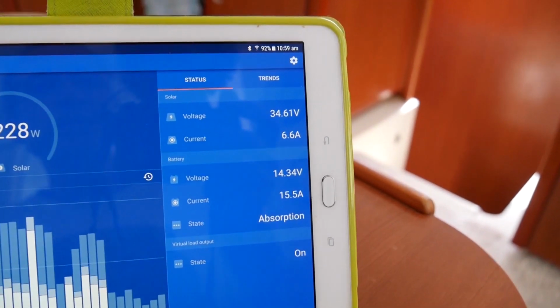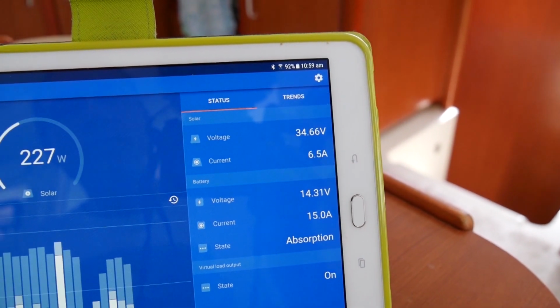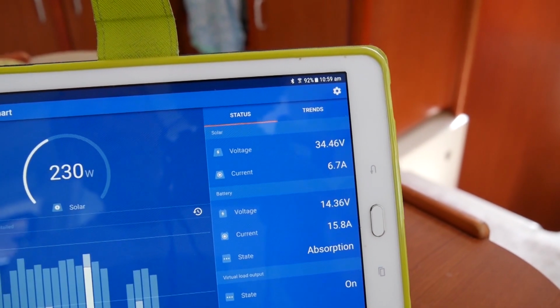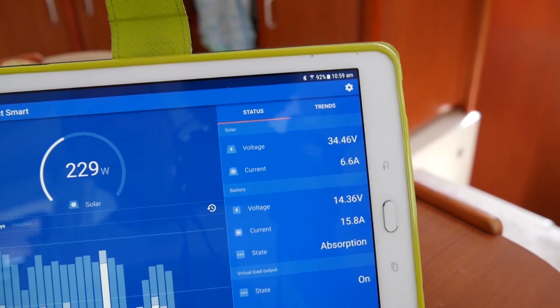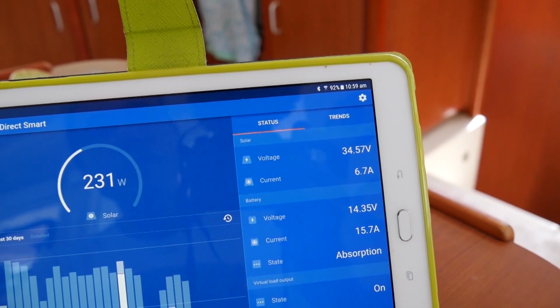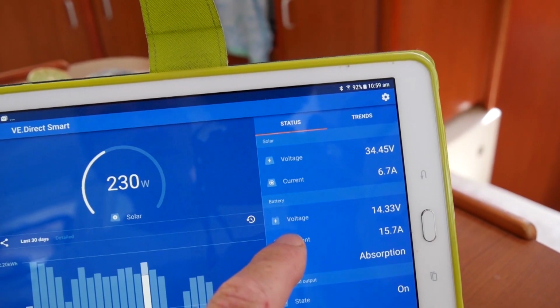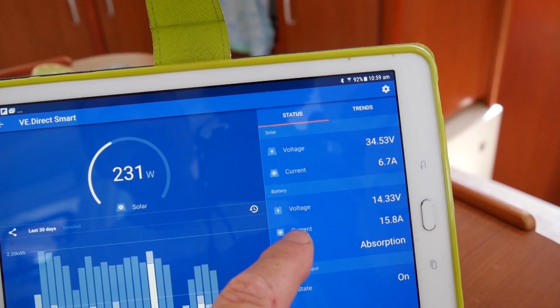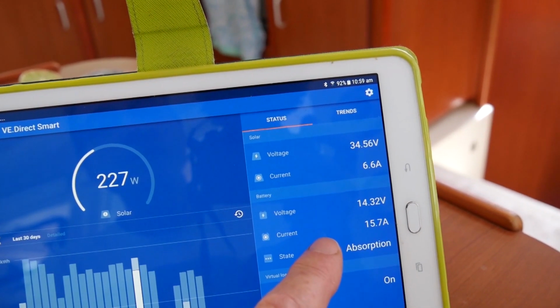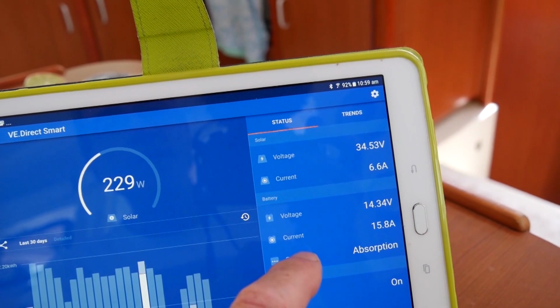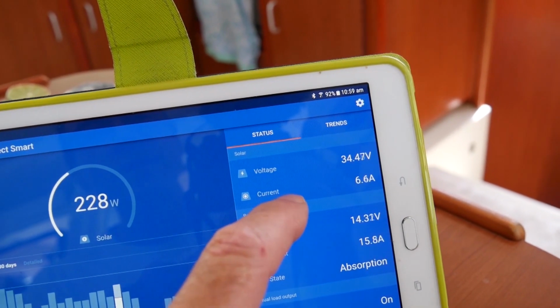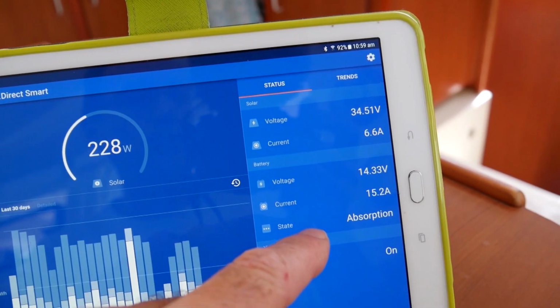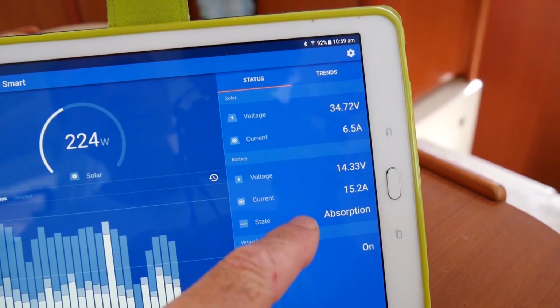And if you look over on this side, it tells us the current voltage, the current that's coming in at that panel voltage, which is 34.5 volts. Down below it shows us how the solar controller converted that to 14.32 volts at a higher current. So the current here is 6.6 amps, the current down here is 15.6 amps.